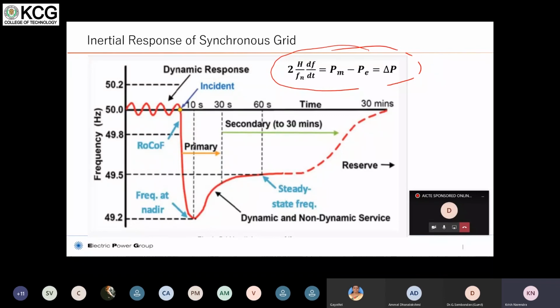When this phenomenon happens, because of the rotational kinetic energy stored in the rotors of the synchronous machines, it can be motors, condensers, or synchronous generators. All the rotating machines which are connected synchronously have the capability of having inertia in them. This inertia will be utilized to support the power that is lost in the grid, or acceleration or deceleration can happen depending on whether the load or the generation is in excess.